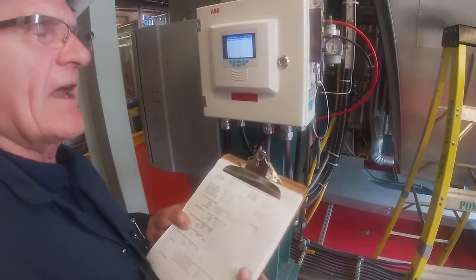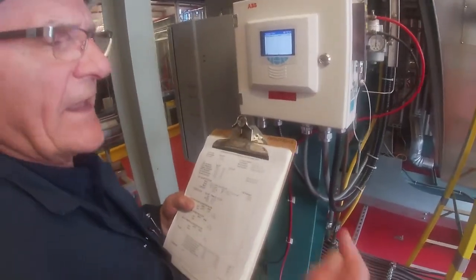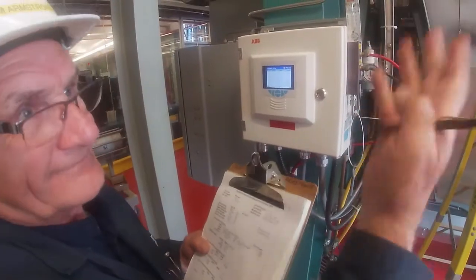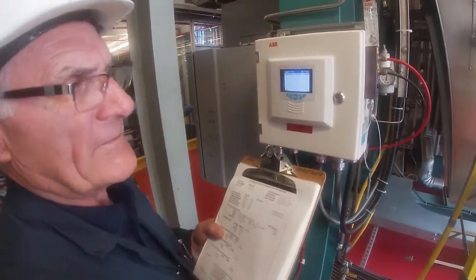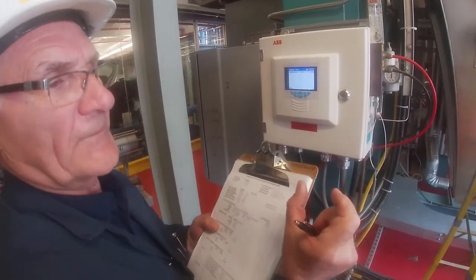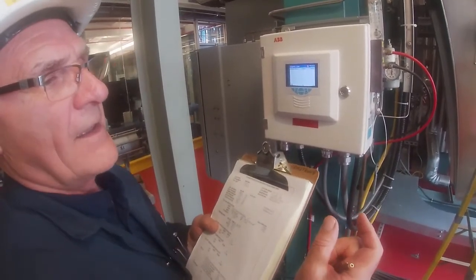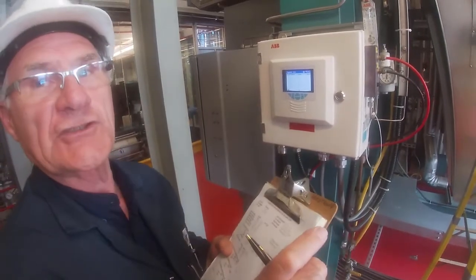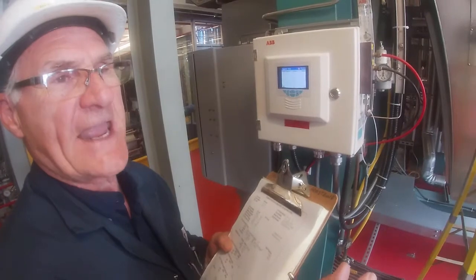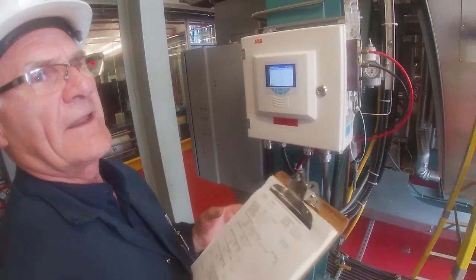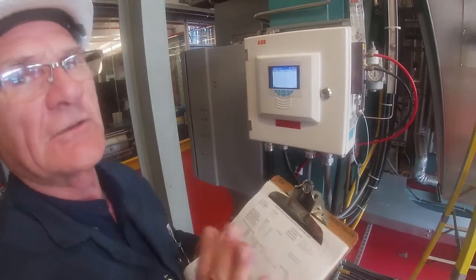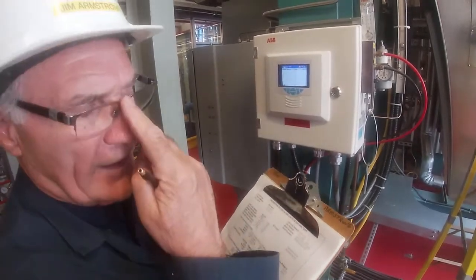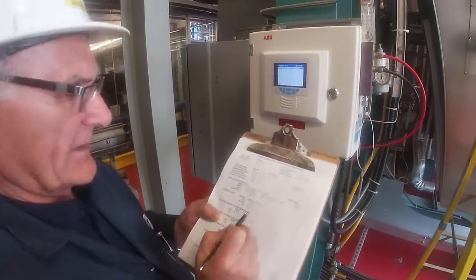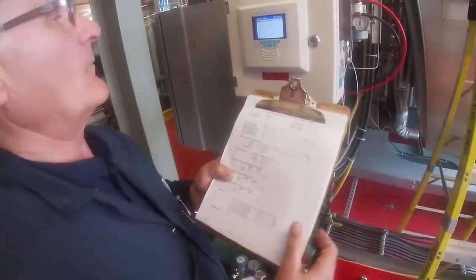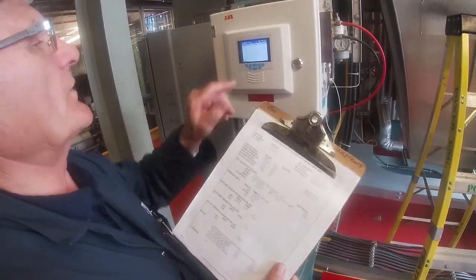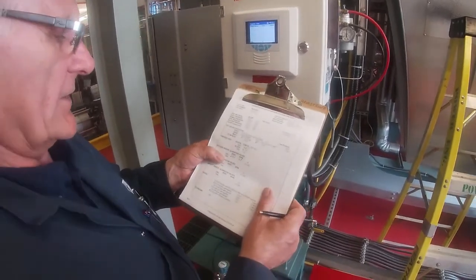With the zirconium oxide cell, inside the cell you've got reference air, atmosphere, at 20.9% oxygen. Outside the cell, you've got your boiler flue gas or sample gas that we're putting in here right now. If there's a difference between them, there's going to be a high millivoltage across it. If they came up to exactly the same, then there would be no millivoltage across it. Now, just like a pH electrode, it's not absolutely perfect, and there's something called an asymmetry error in it. That's why I've got the minus 3.8 on there when I've got no differential across it.